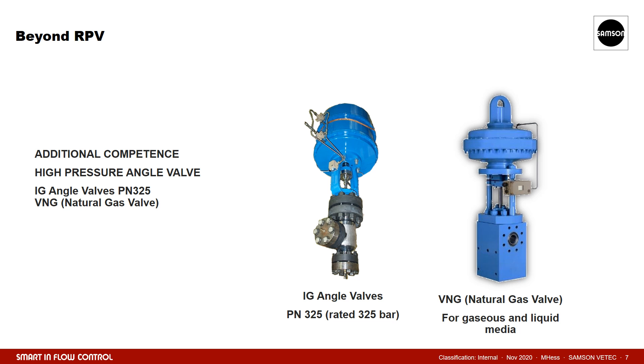The other high pressure angle valve series produced at Vetec is the type VNG. It was once designed to control natural gas at the wellhead. Nowadays, it is a classic choke valve that can control gases as well as liquid media. Its main feature is the ability to handle a pressure drop of several hundred bar with a single stage design trim.